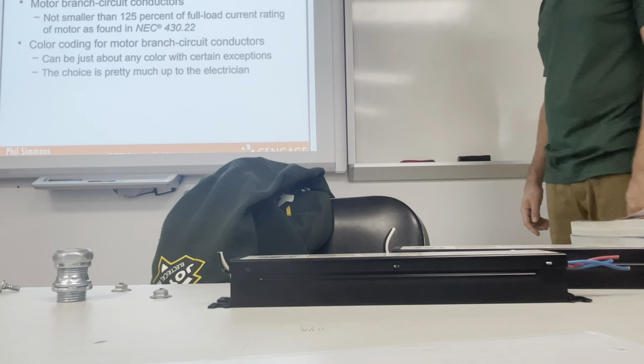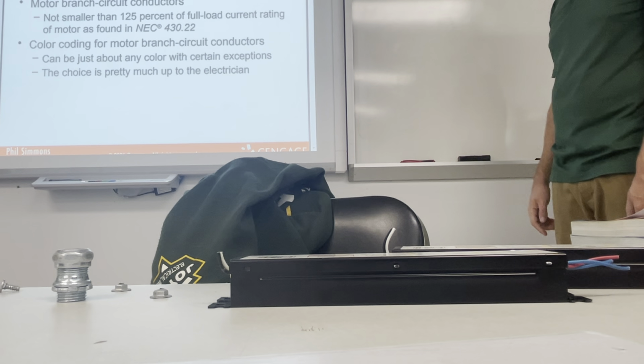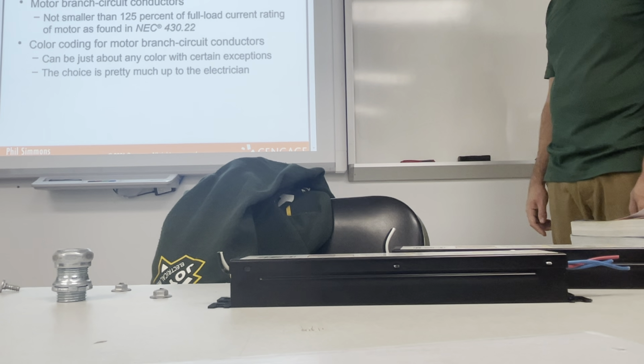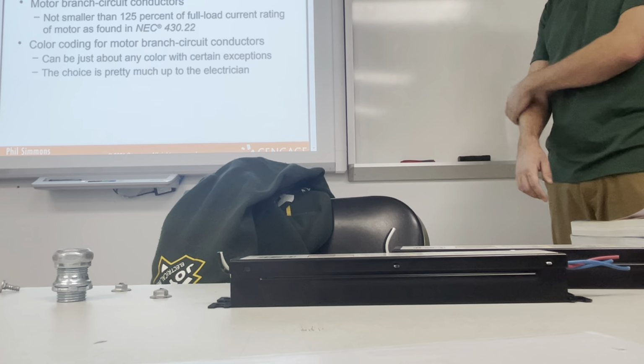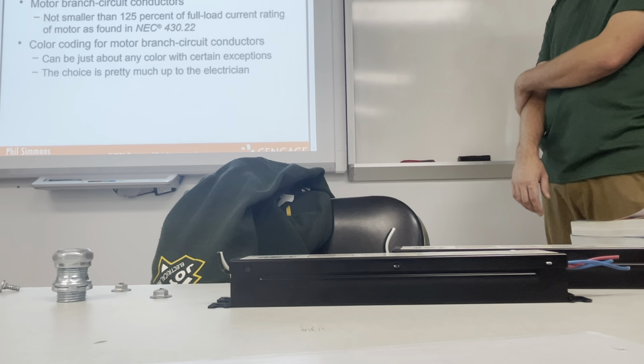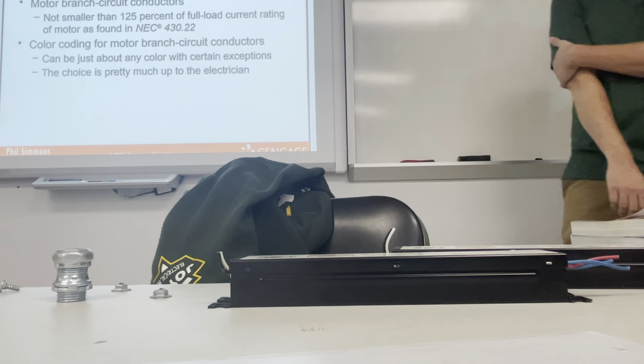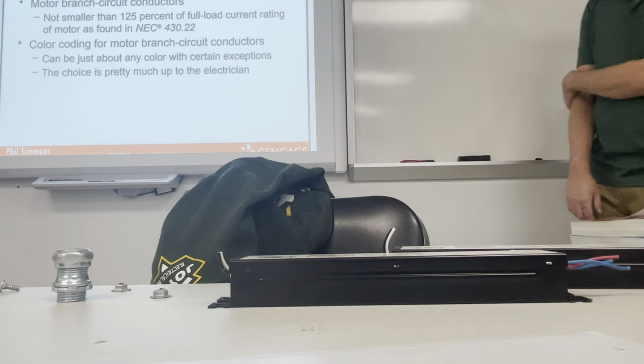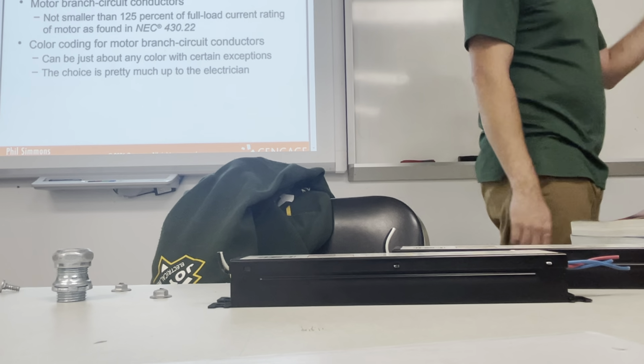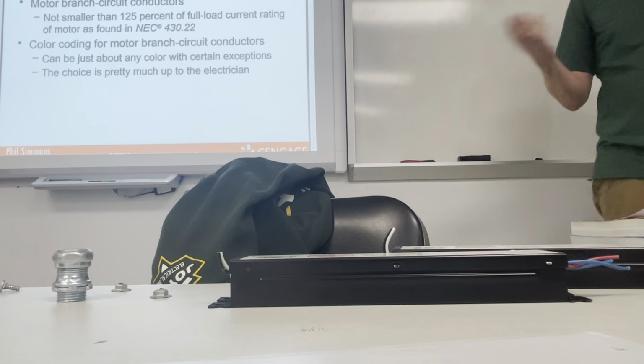Basics of motor circuits. Motor branch circuit conductors not smaller than 125% of full load current rating of motor, as found in NEC 430.22. Color coding for motor branch circuit conductors can be just about any color with certain exceptions. The choice is pretty much up to the electrician. Yeah, but once again, if you can keep those colors proper, it's not going to hurt anything. Not smaller than 125%. When you're looking at a 3-phase motor, just think 125% off the top of your head. Just envision that can be continuous load and upsize your wire accordingly.